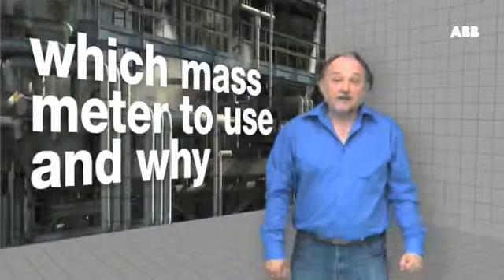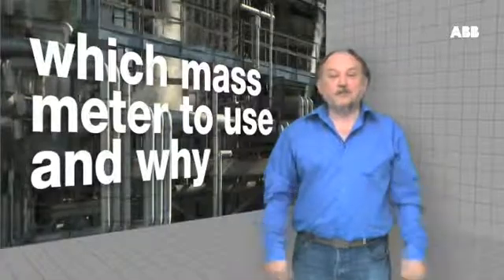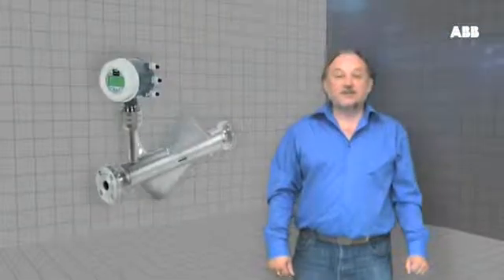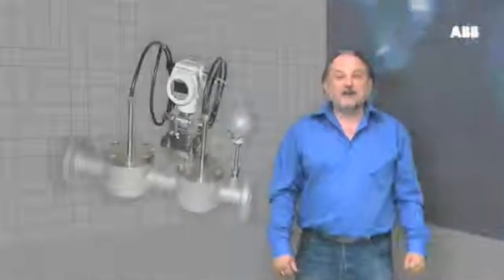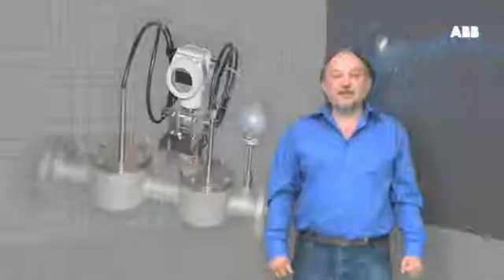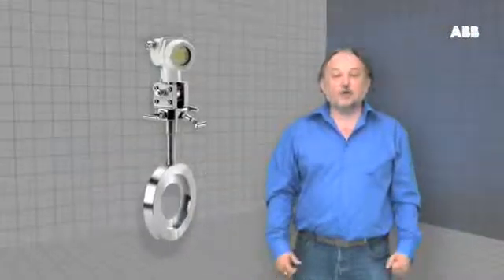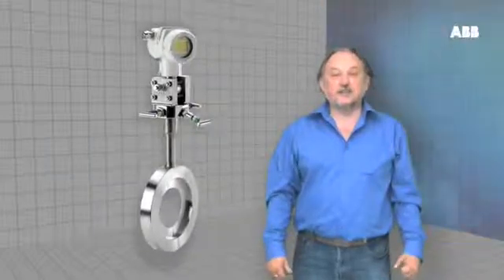In summary, this is what you need to remember about mass meters for various applications. For liquid mass flow measurements, especially where variations in product density are common and the product is priced by weight, Coriolis meters should always be considered. Their high accuracy and repeatability means excellent cost savings, and because product density can be measured, the quality of the product or even its identity can be assessed.